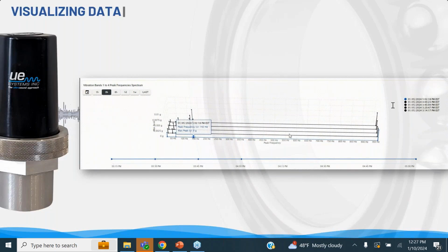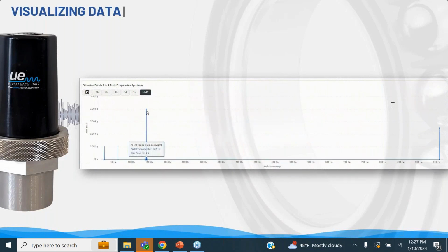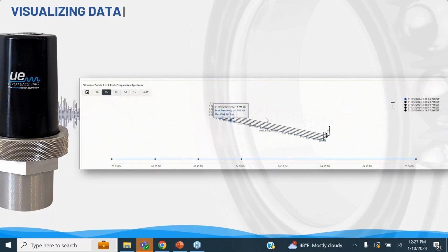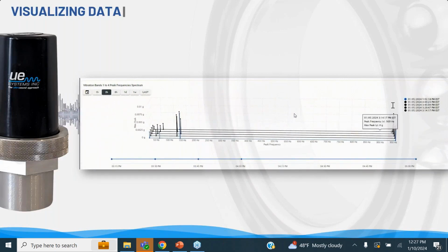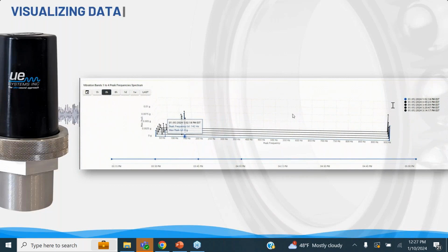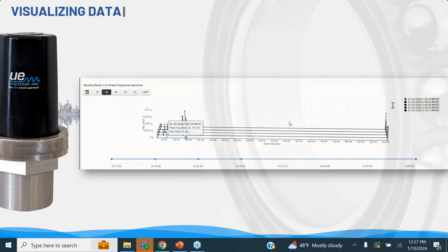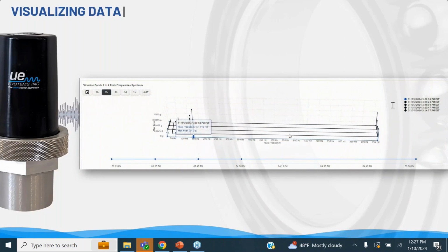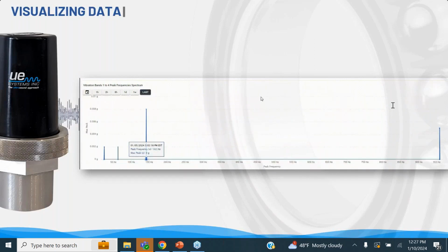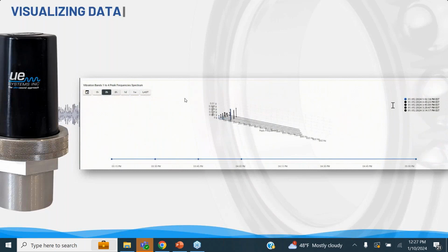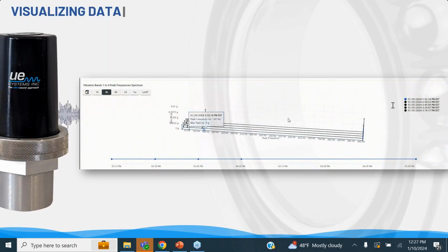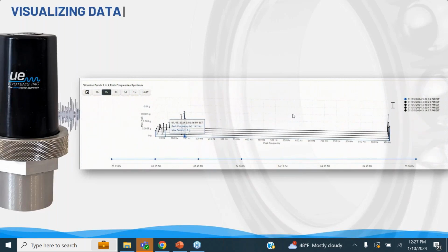As you can see here with this waterfall plot, you can look at that change over time. We have frequency versus the max peak of the acceleration. Very specific bands: 1-times orders, 2-times orders, bearing harmonics, things like that. We can plot it over time and you can see that change over time. So no longer are we limited to just a single axis of information. We can look at it as a vibration analysis or an ultrasound analysis person would do.